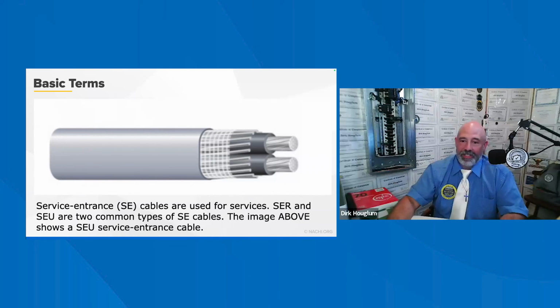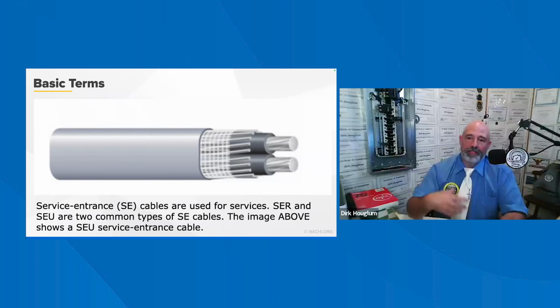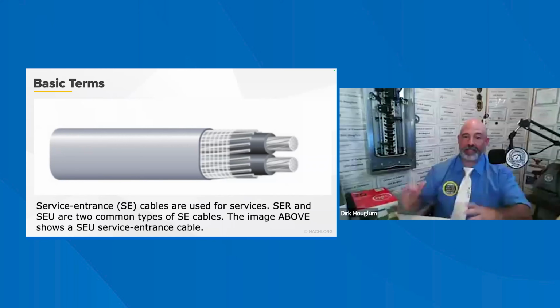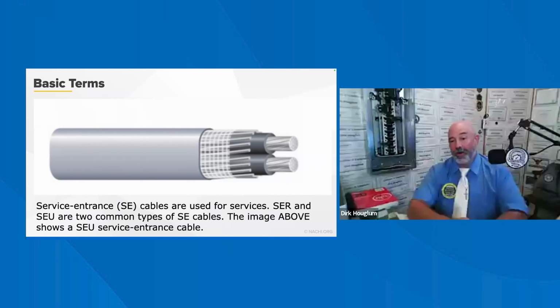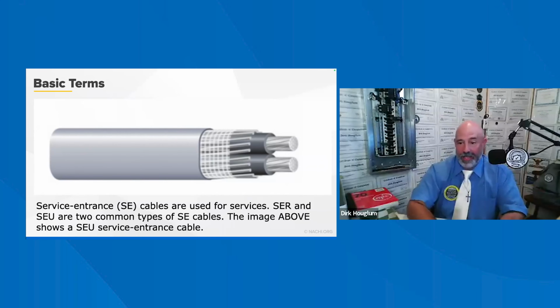The SE and the SEU service entrance cable is primarily used to convey power from the service drop to the meter base, and then to the distribution panel board, then to the main disconnect installed at the main power board. Okay. SEU is the service entrance unarmored three-wire cable, two conductors and a neutral, typically an oval shape because the stranded neutral conductor wraps around the cable to create an oval shape.